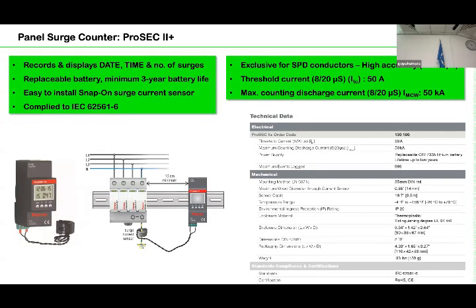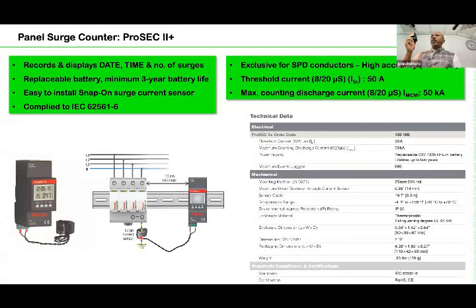So basically, this is a surge counter. Most of the time, customers, especially industrial and telecom customers, ask: I have installed an SPD, but I don't know whether there is a real surge or not. So this is a device, as you can see here, on the earth wire, there is a kind of CT. Whenever there is a current flow, this device will record it. You can see the date, time, duration, and the number of counts.